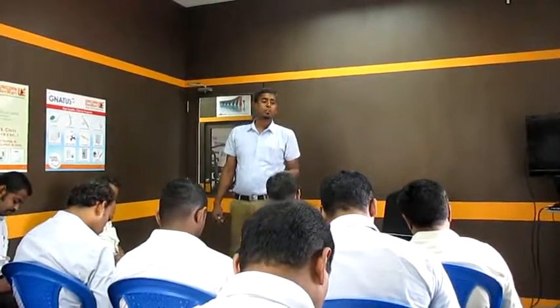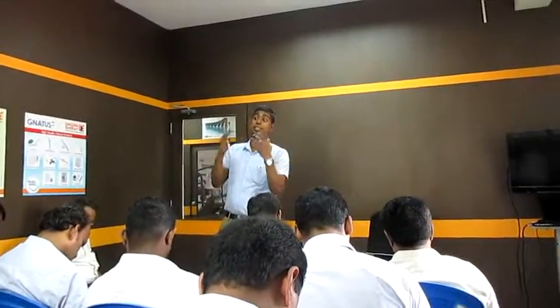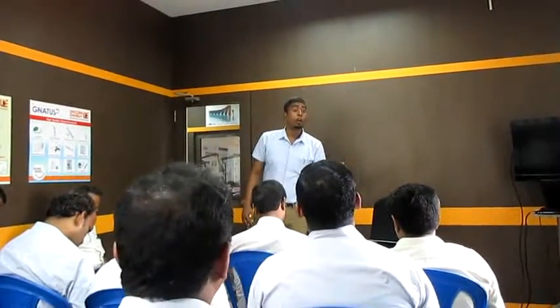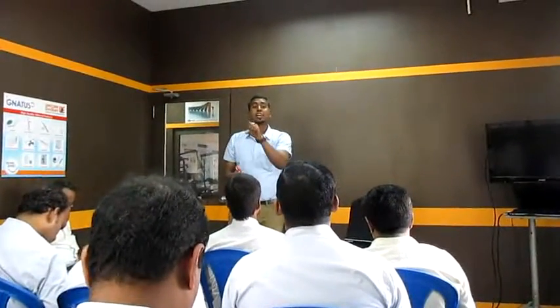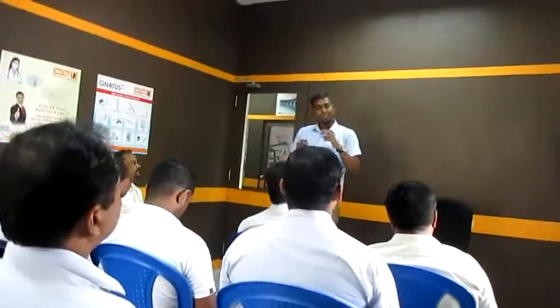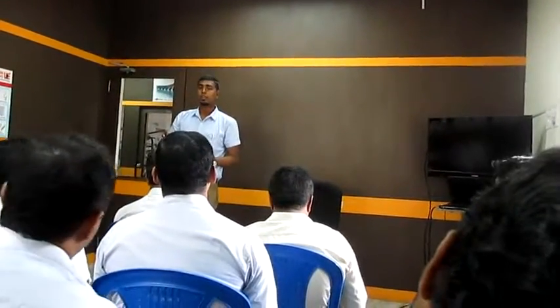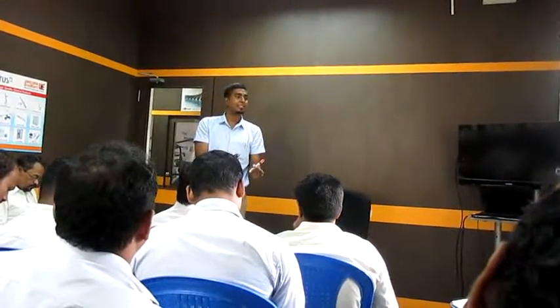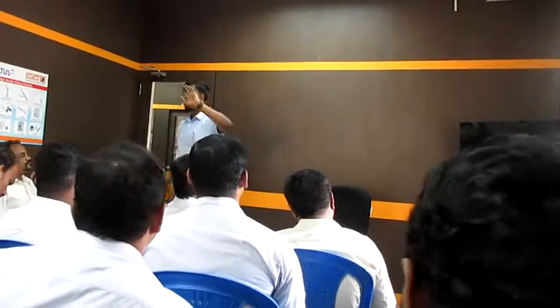This is a standard. Now the competitors are saying 2 mm of aluminum. What will happen if you place a 2 mm aluminum filter for 70 kVp X-ray? It will start stopping the useful X-ray also. It will consume more. It will start absorbing the hard X-ray also. We don't want to absorb the hard X-ray, right? So as per the guidelines, we are satisfying the guidelines. This is our AERB guidelines.